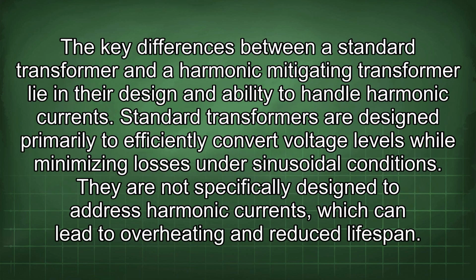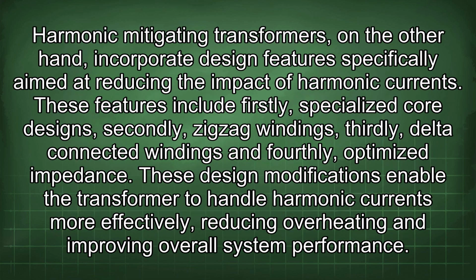The key differences between a standard transformer and a harmonic mitigating transformer lie in their design and ability to handle harmonic currents. Standard transformers are designed primarily to efficiently convert voltage levels while minimizing losses under sinusoidal conditions. They are not specifically designed to address harmonic currents, which can lead to overheating and reduced lifespan. Harmonic mitigating transformers, on the other hand, incorporate design features specifically aimed at reducing the impact of harmonic currents. These features include, firstly, specialized core designs, secondly, zigzag windings, thirdly, delta-connected windings, and fourthly, optimized impedance.